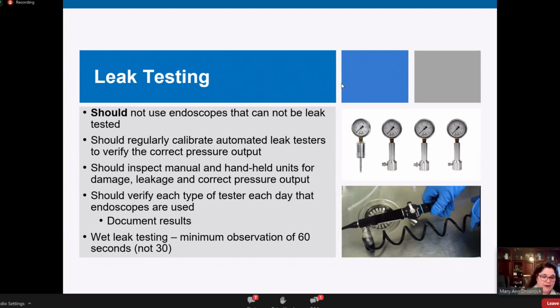And per the IFU, you're running your hands over the scope. It really does take that long to do a critical evaluation to see if there are any bubbles anywhere coming out of that endoscope. So that's a big change, and that more aligns with what the rest of the world is already doing for a leak test when you do a wet leak test submersion.